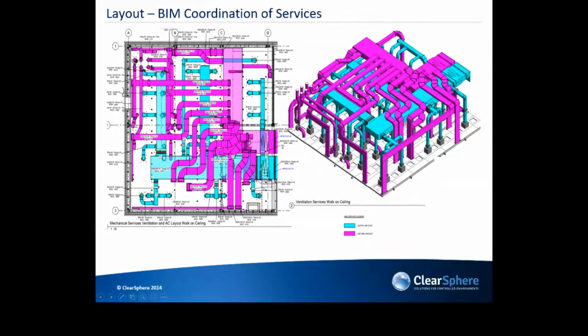You have the individual isolator extracts dotted around the compounding area, above the compounding ceiling, and they all extract through the roof of the building. That gives you a view of the amount of coordination that needs to be done.